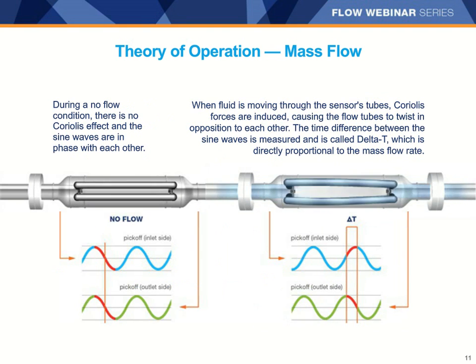During a no-flow condition, there is no Coriolis effect and the sine waves are in phase with each other as illustrated in the picture on the left. When fluid is moving through the sensor's tubes, as shown on the right, Coriolis forces are induced, causing the flow tubes to twist in opposition to each other. The time difference between the sine waves is measured and is called delta T, or time delay, which is directly proportional to the mass flow rate.